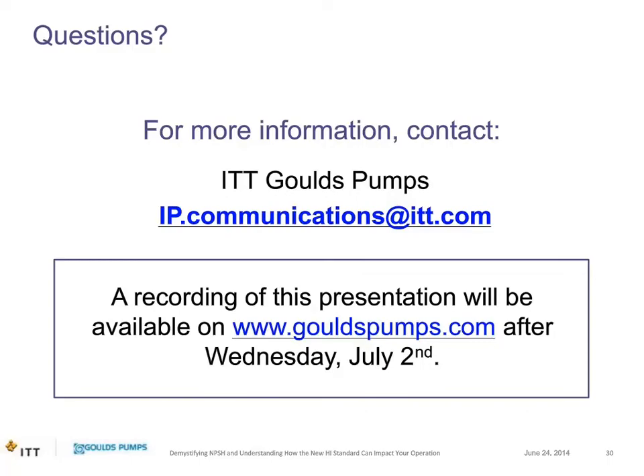Question: How do solids influence the NPSH calculation? They don't — provided the solids stay in suspension. Solids affect pump life, material selection, and pump selection (slurry vs. process pump), but from an NPSH calculation standpoint, you go back to the standard NPSH available equation: surface pressure, static height, vapor pressure, and head losses. The addition of solids does not affect the NPSH calculation.